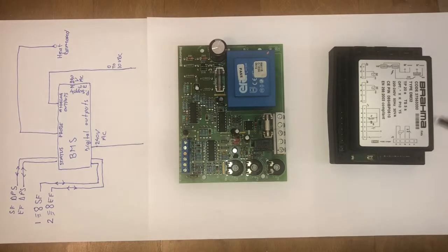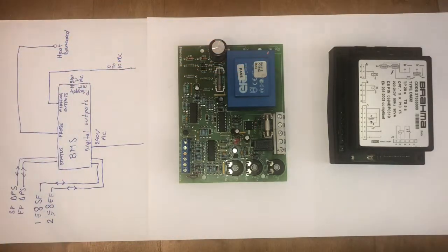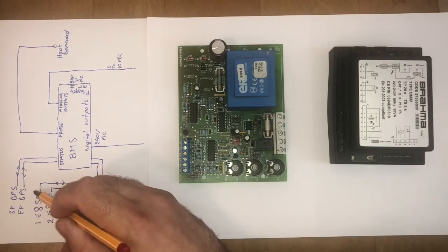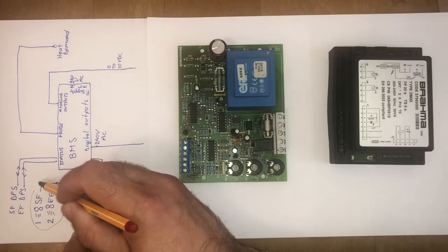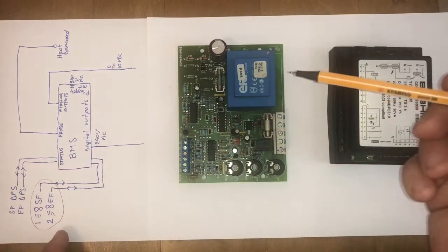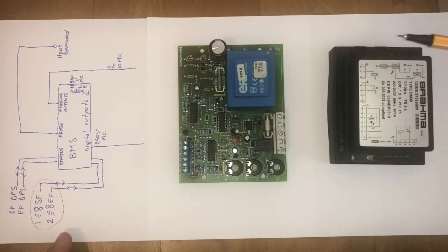The building management control, and I'm going to use the red pen this time, first has to enable the supply and the extractor fan, because it is pointless to start a flame if the air is not passing through the indirect heater, because the flame goes through some tubes.